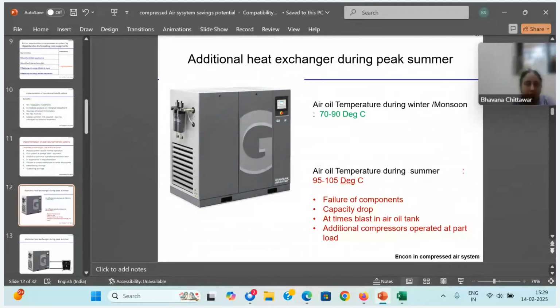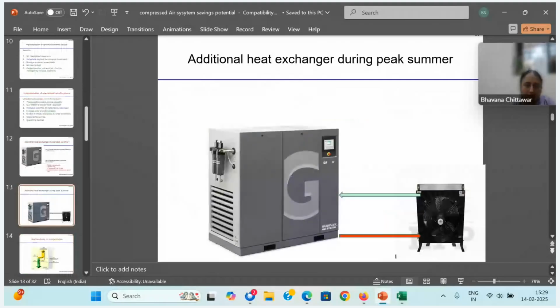He said, same problem. So what I've done, they had a spare heat exchanger. Immediately I took the spare heat exchanger and modified the oil circuit. I put the extra heat exchanger in the circuit with temperature control. This extra heat exchanger will not run always. Whenever the air oil temperature rises, the fan will run. Otherwise, only the oil will pass through it. So no additional energy is consumed during normal conditions. Only during peak condition or peak daytime, the fan will run. So you can maintain the temperature within the preset required level. See, these OE suppliers will not recommend it, but we can do it. We have done it in many clients. I'm recommending this to many suppliers.